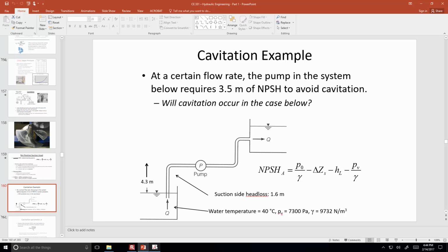The ways to prevent it would be to reduce the flow rate, which would decrease the head losses on the suction side of the pump. Sometimes to prevent cavitation, they'll make the suction pipe a really large diameter. The reason is that a large diameter pipe on the suction side decreases the velocity, so there are fewer head losses. That's just another way of minimizing the head losses.